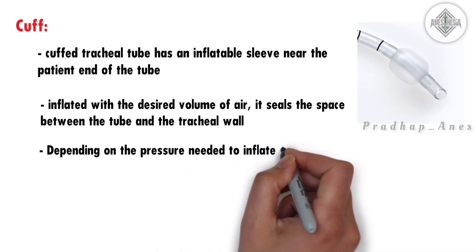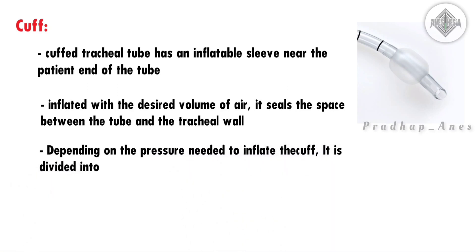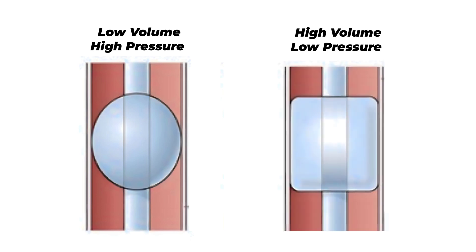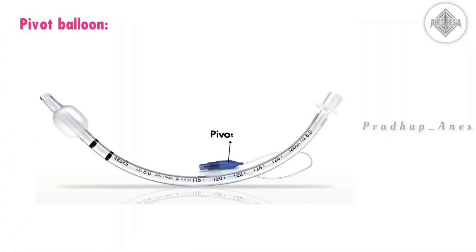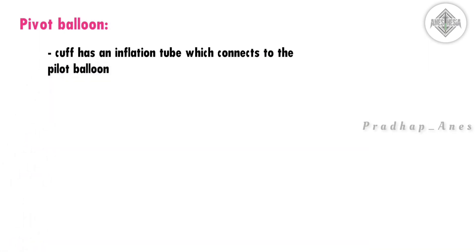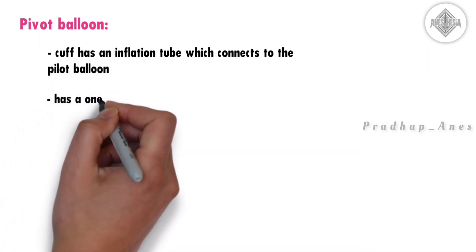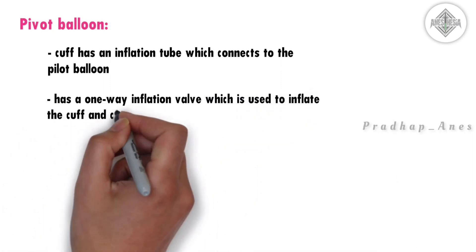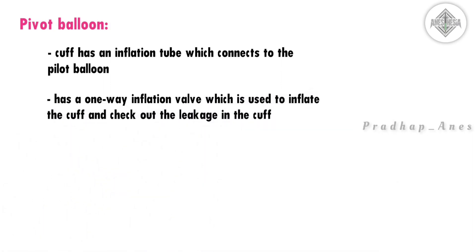Cuff types. Depending on the pressure needed to inflate the cuff, it is divided into low volume high pressure cuffs, and high volume low pressure cuffs. The cuff has an inflation tube which connects to the pilot balloon. This pilot balloon has a one-way inflation valve which is used to inflate the cuff and check for leakage in the cuff.